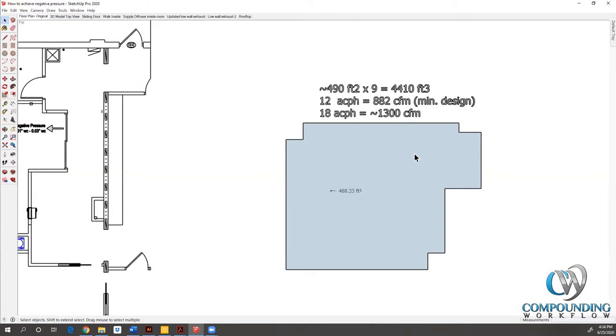Some have said, well, on a negative pressure room we actually want to measure the exhaust. That's not always the easiest thing to do. Typically, if you are achieving 12 air changes per hour at the ceiling, and we know that it requires more air out of the building to achieve negative pressure, then of course you are going to be above 12 air changes per hour. If you can hit it at the supply, you're definitely going to maintain it at the opposing side, which is the exhaust side.